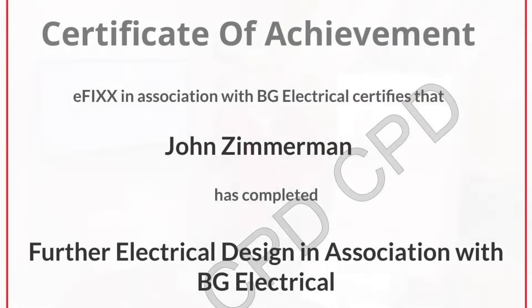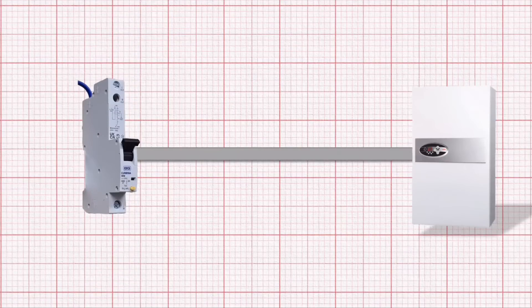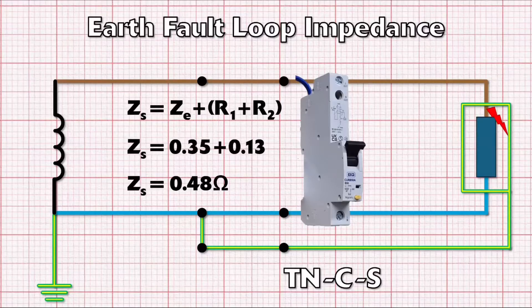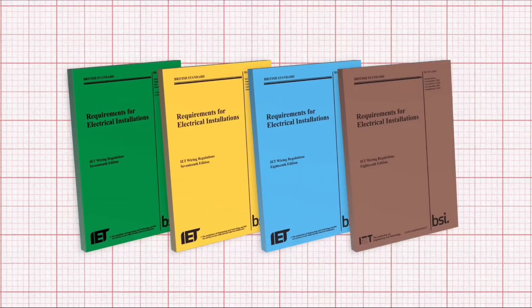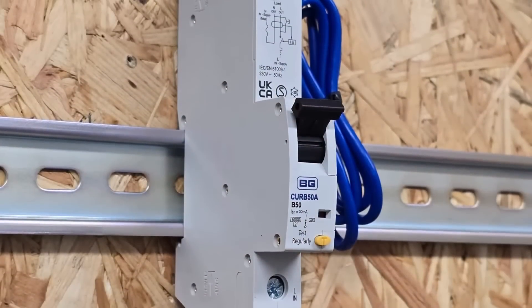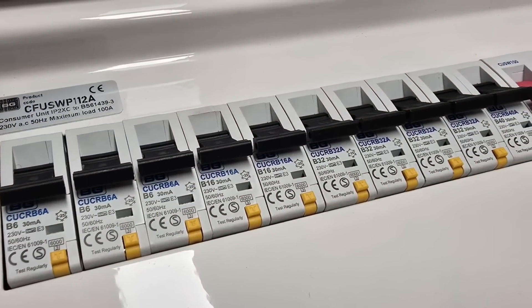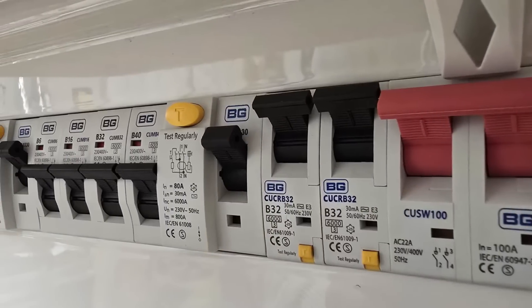You'll receive a certificate to prove you've completed the course. Throughout this design process we've protected our circuit using an MCB and based all our calculations around that - but does our circuit need RCD protection, and if so how does that affect our carefully crafted calculations, particularly when it comes to earth fault loop impedance? The last few amendments of the wiring regs have increased the stringency of requirements for RCD protection, and it's becoming increasingly common for circuits to be protected by an individual RCBO. While the gold standard is individual RCBOs, split load boards can still be made compliant.